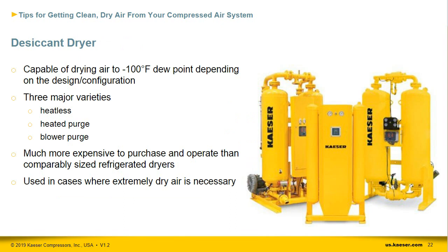Desiccant dryers use a different technology to provide dry air. Much like refrigerated dryers, there are different types of desiccant dryers, and all varieties dry compressed air the same way. They only regenerate via different methods. We'll get into some of the differences between heatless, heated purge, and blower purge dryers later. In general, desiccant dryers are much more expensive to purchase and operate than comparably sized refrigerated dryers. They do provide a much lower dew point than refrigerated dryers, but at an increased cost.